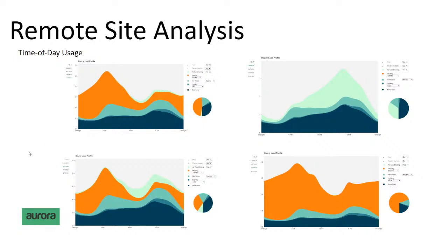So how do you get your load profile information? If you're backing up a critical load panel, what's your maximum load going to be? Either you're being very conservative in what you're putting on that critical load panel, or you're actively managing the power on that panel to do some load shifting. There's no better way to capture this data than to put a service panel monitor in your service panel and monitor the circuits before you do a battery backup project.